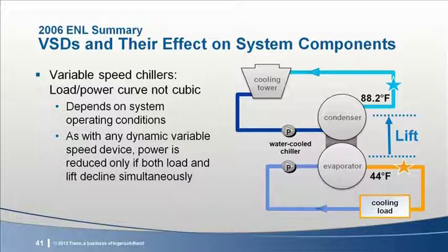The reduction in compressor lift is limited by a number of factors. The first is outside wet bulb temperature. The system condenser water temperature can only decrease if the wet bulb temperature decreases. We've begun to term this as the wet bulb opportunity. As I'm sure you understand, this wet bulb opportunity does not necessarily follow the chiller's load profile.